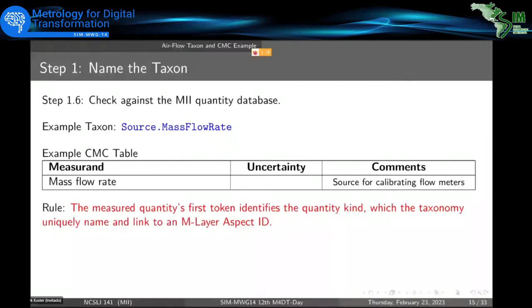So then we just add further taxons to further qualify our measurand. We're going to calibrate mass flow rate of gases with ambient air, and in our CMC we can add that information too. We'll do it either with ambient air or dry nitrogen.